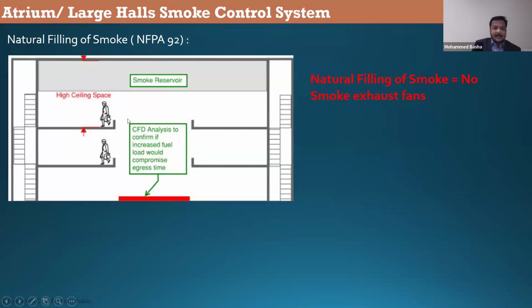If you don't have these atrium spaces, like the communicating spaces here, then you could use this system to get the time needed for the smoke to descend down to this level. For example, if you need 180 seconds for the smoke to come down to this level, you need to see the occupant evacuation time at this level, how long they need to evacuate from this space. If the evacuation time is less than the smoke filling time, then you could use the system, but it must be analyzed well with CFD analysis.